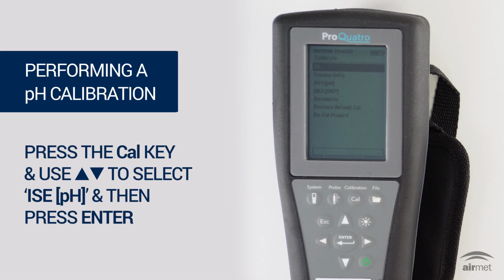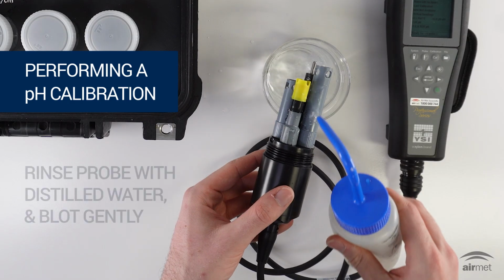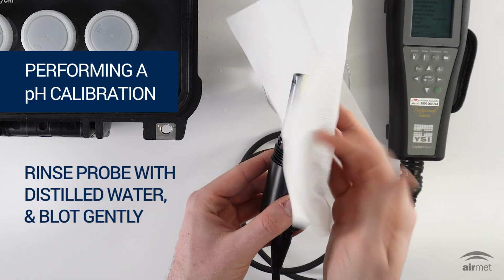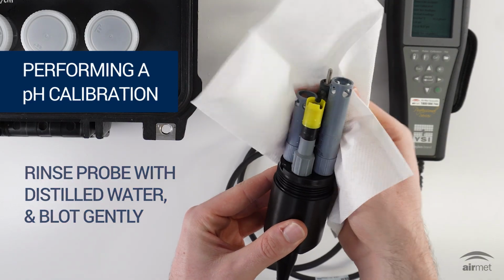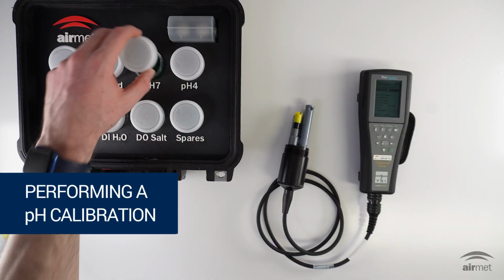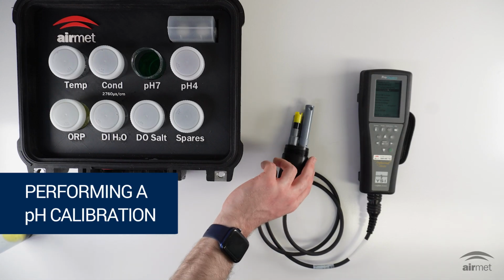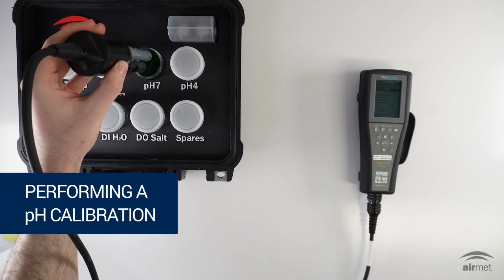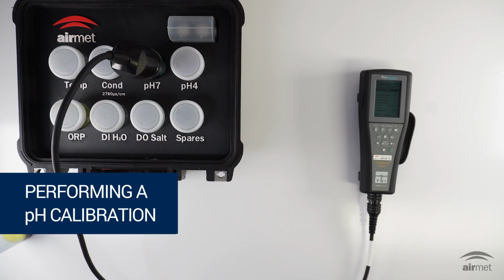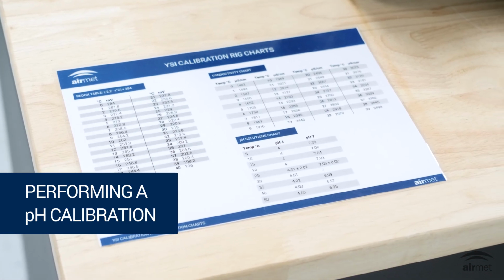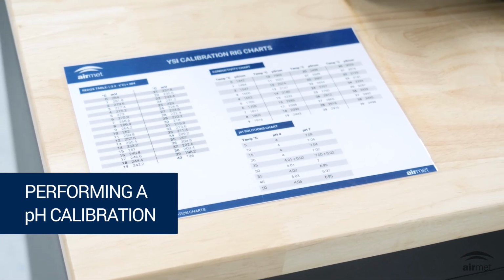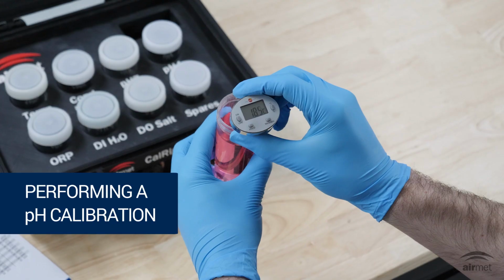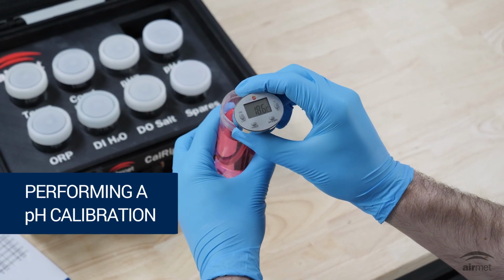a strict requirement. For your first calibration point, press Cal and highlight the YSI pH probe and press Enter. Rinse the probe with distilled water and blot gently. Then place the probe in the first buffer solution, pH 7 in this case. Reference the included temperature versus pH chart for buffer solutions provided by AirMet Scientific. A thermometer is recommended when calibrating the sensors to verify the temperature probe.